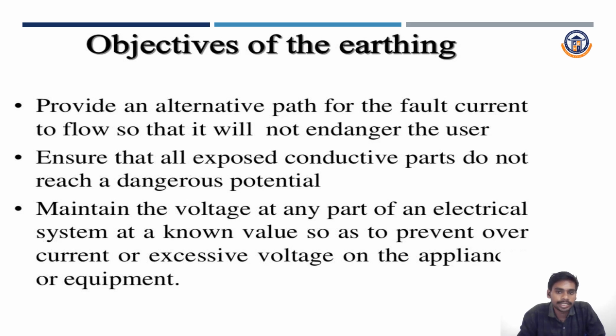Objectives of earthing system. Provide an alternative path for the fault current to flow so that it does not endanger the user, because the current will always choose the low resistance path. Ensure that all exposed conductive parts do not reach a dangerous potential. Maintain the voltage at any part of an electrical system at a known value so as to prevent overcurrent or excessive voltage on the appliances or equipment.